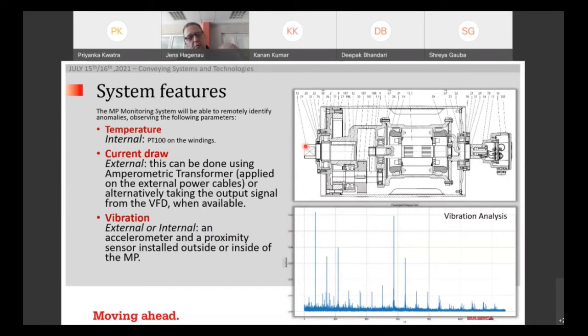and from the normal run of the motor, there is a motor-specific temperature curve, and here we can easily see deviations, which gives us the information that there could be something wrong inside of the motor, or maybe something wrong with the load of the conveyor permanently. The second point is checking the amperage of the motor. What is the current? Also, there are normal values, and we can also see very well if something has happened when there's too big a deviation in the amperes.